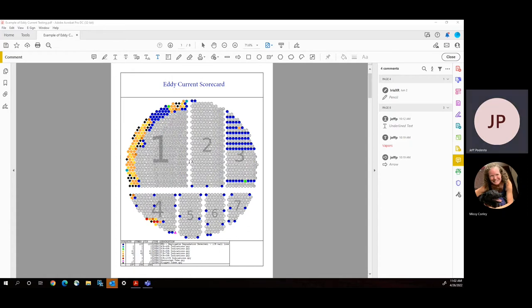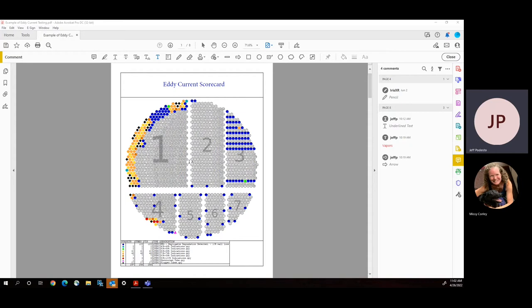Eddy current testing provides mechanical integrity analysis along the entire length of the evaporator tube. That's the important part because we're able to read the entire length, determine whether there's a particular depth in which we're seeing mechanical failure or whether those failures are all along the complete length of the tube, which usually tells us whether there's corrosion issues or mechanical issues with the tubes. I'm going to take you through a test real quick, and then I'll give you a little feedback on a couple of these that we've done so that you can see what we've been able to achieve through eddy current testing.